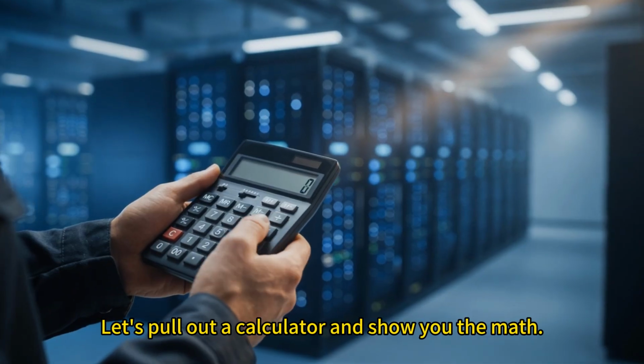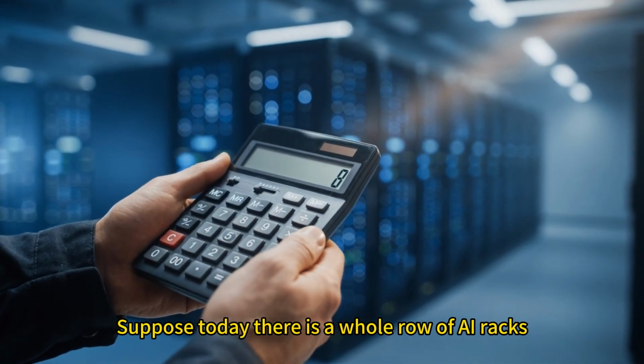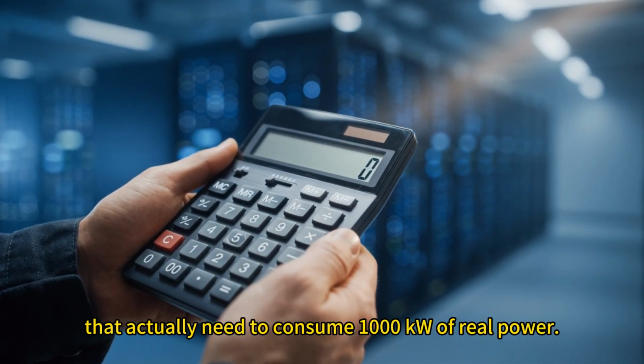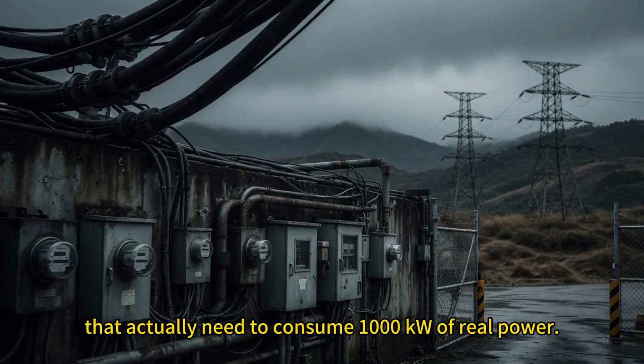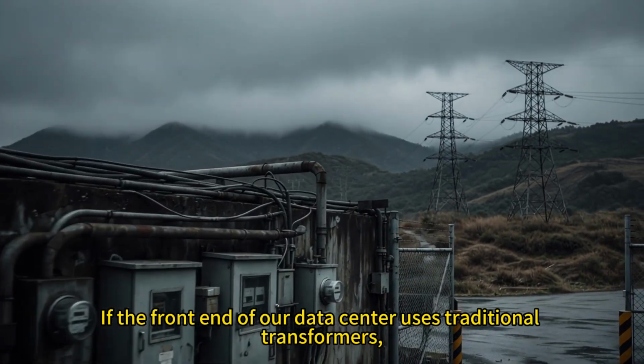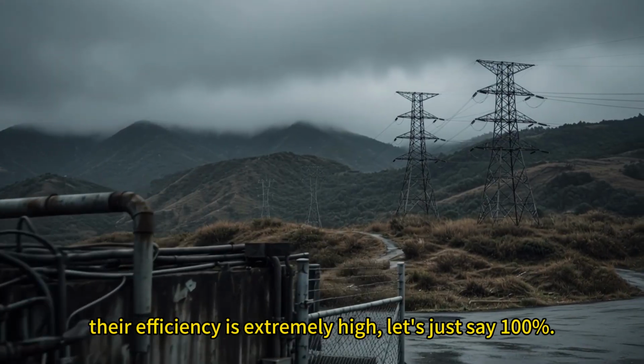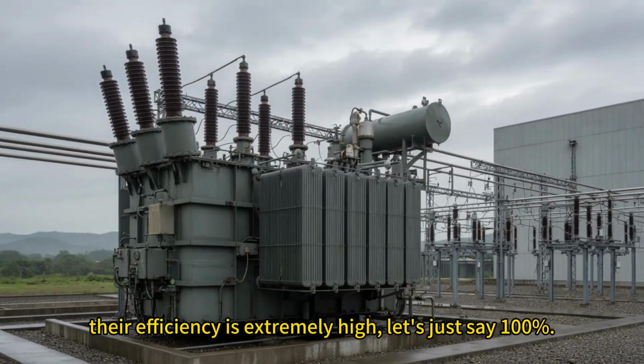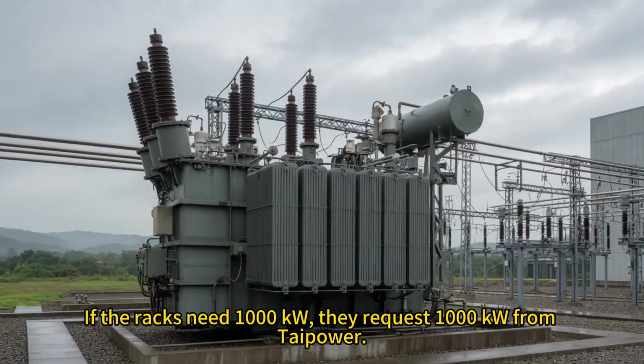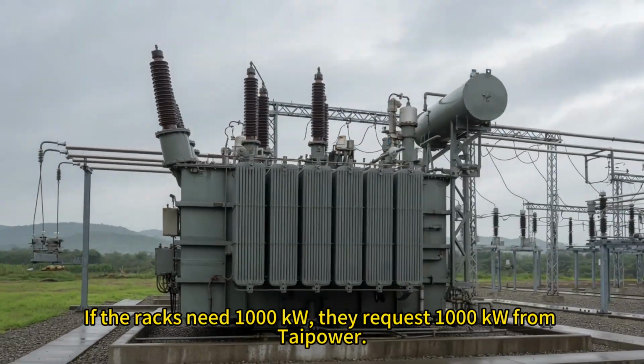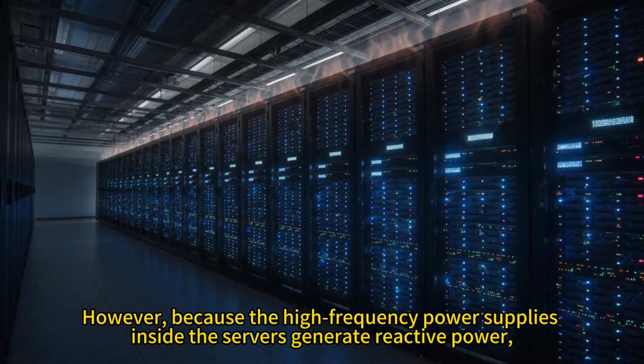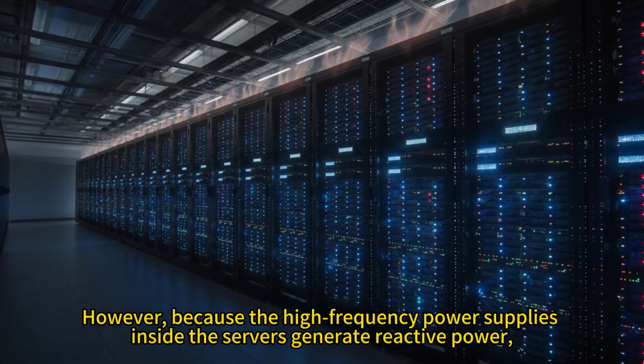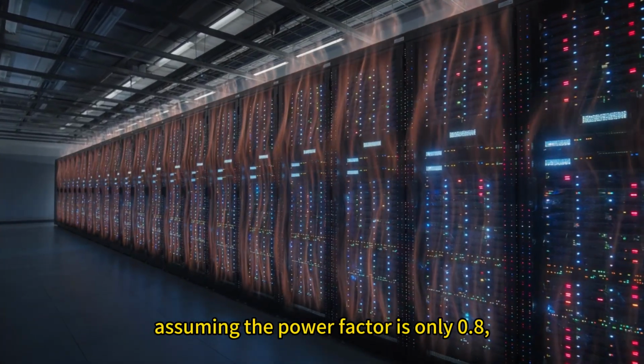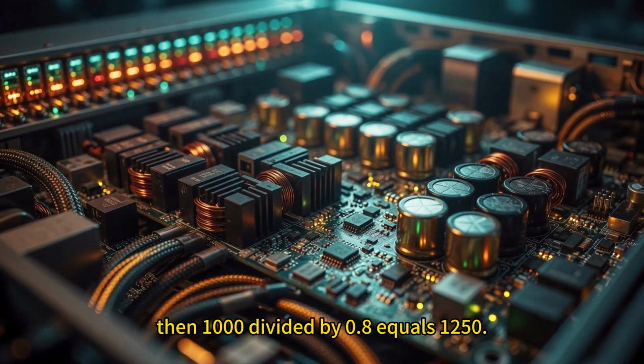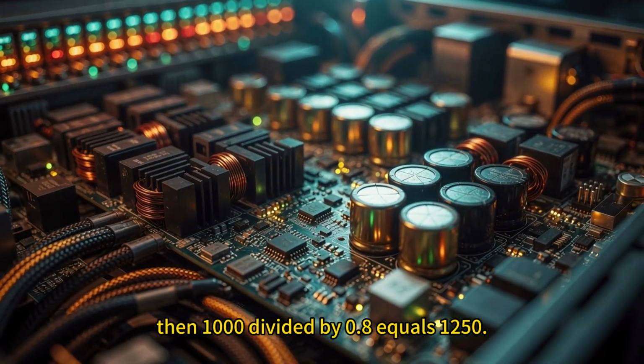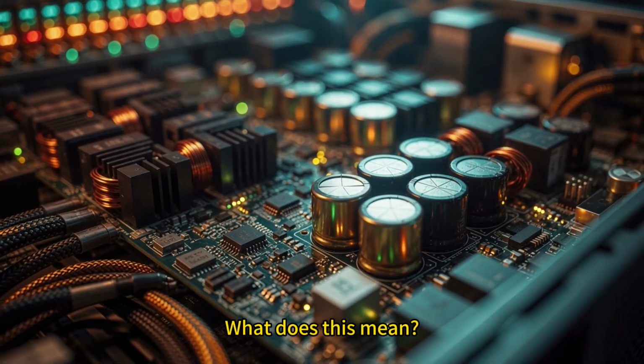Let's pull out a calculator and show you the math. Suppose today there is a whole row of AI racks that actually need to consume 1,000 kilowatts of real power. If the front end of our data center uses traditional transformers, their efficiency is extremely high, let's just say 100%. If the racks need 1,000 kilowatts, they request 1,000 kilowatts from Taipower. However, because the high-frequency power supplies inside the servers generate reactive power, assuming the power factor is only 0.8, then 1,000 divided by 0.8 equals 1,250. What does this mean?